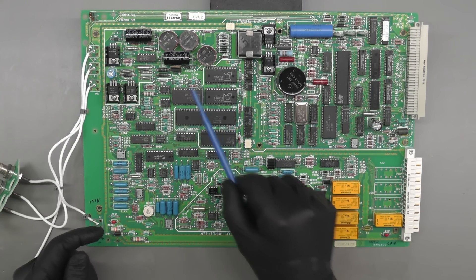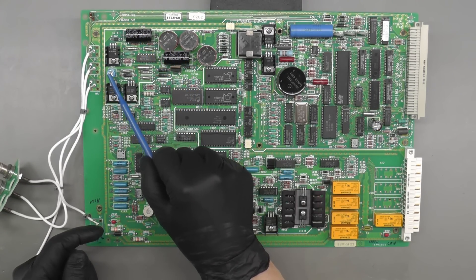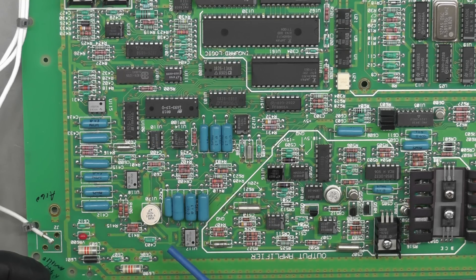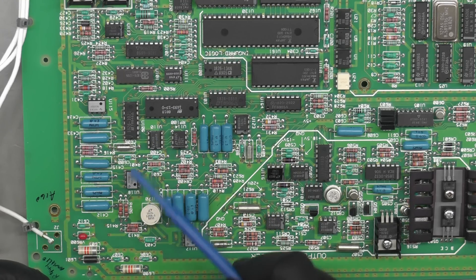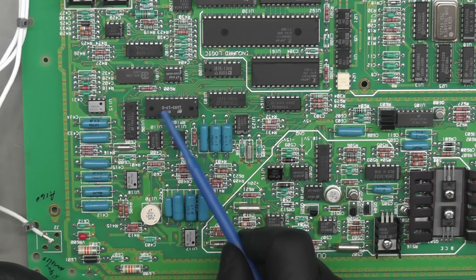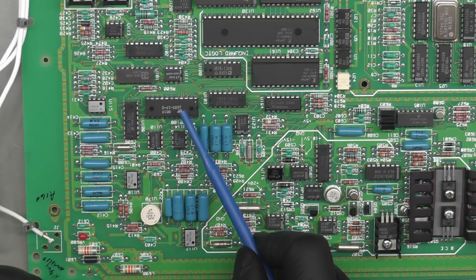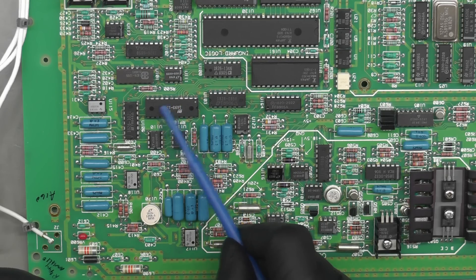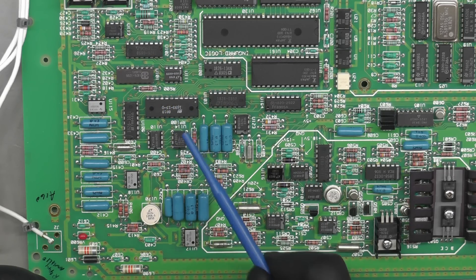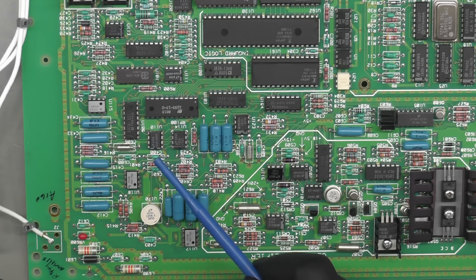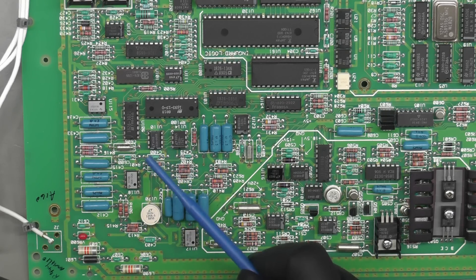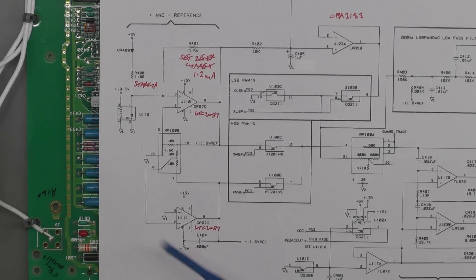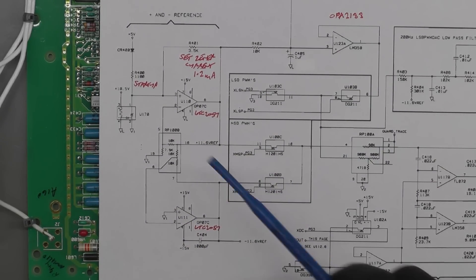Right, I've replaced the electrolytics on the A1 analog board—that one, those two there, and that one there. And here's the Vref circuit roundabout here—there's the LM399 and the associated op-amps are scattered far and wide really, including this rather special resistor package here. Looks like an IC—I believe that's just a resistor package. I'm not going to touch that. What I'm actually going to modify is three of the op-amps. I'm actually going to replace them.